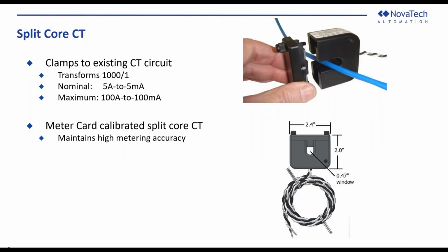Talked about the split core CT. This is, again, an auxiliary CT. It clamps to the existing CT circuit. It's a precise 1,000 to 1 transformer, essentially. And nominally, the circuit would be 5 amp that we clamp around, so that would be converted to 5 milliamp. It does have a very high dynamic range and can go all the way up to 100 milliamp output in the presence of a 100 amp signal, which would be typically seen for a high fault condition.